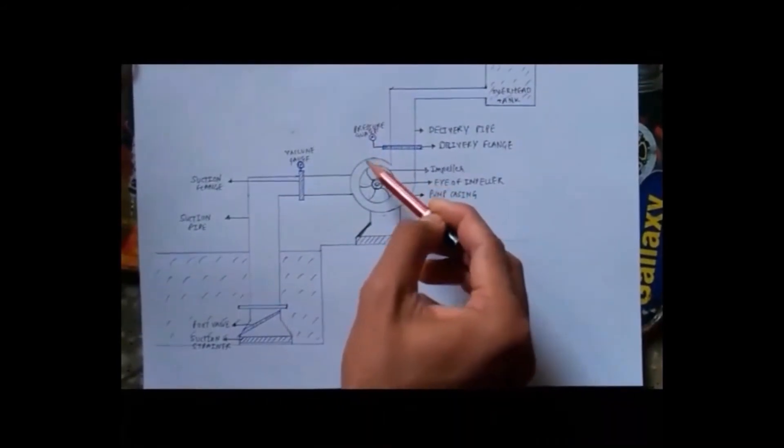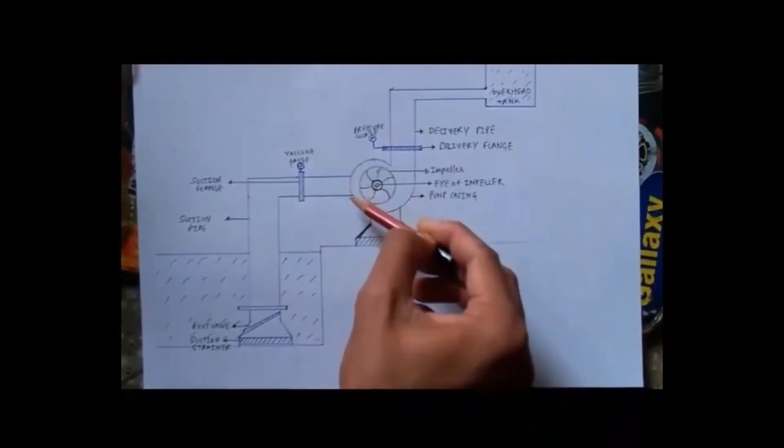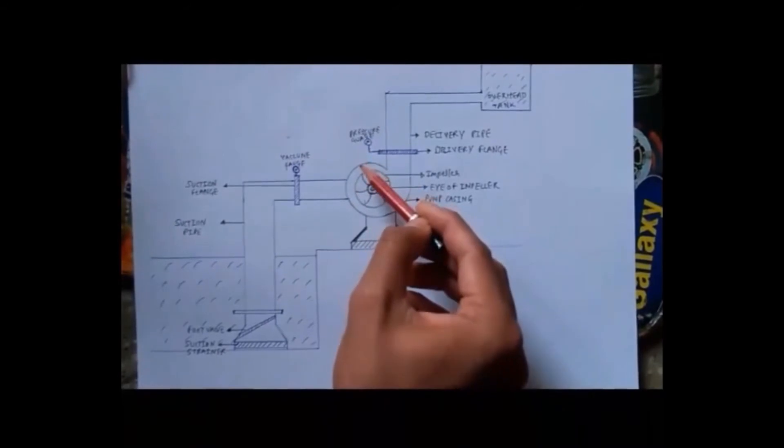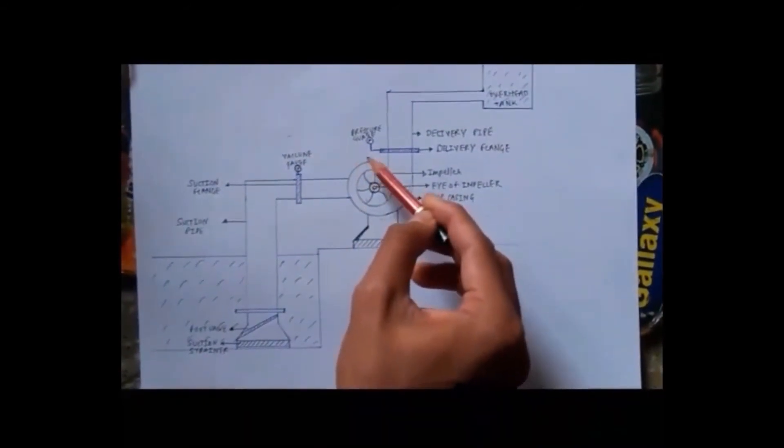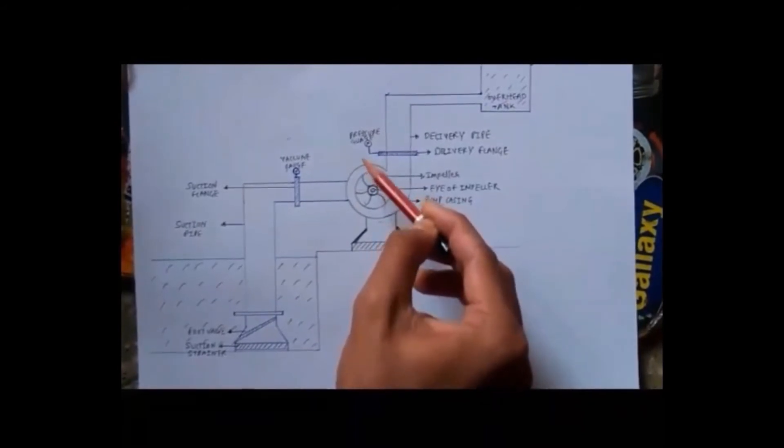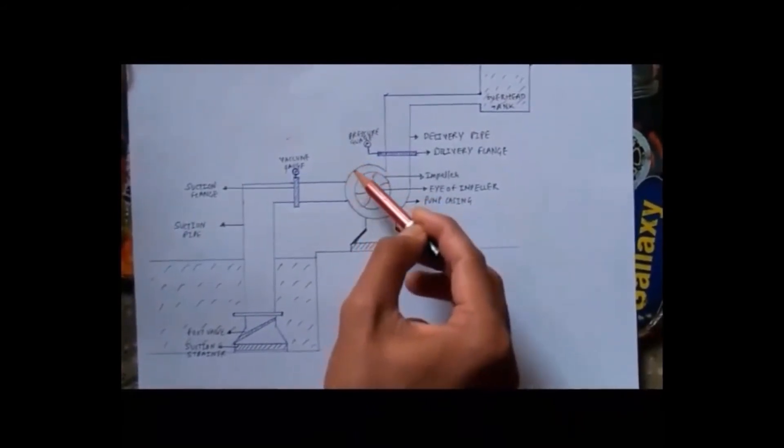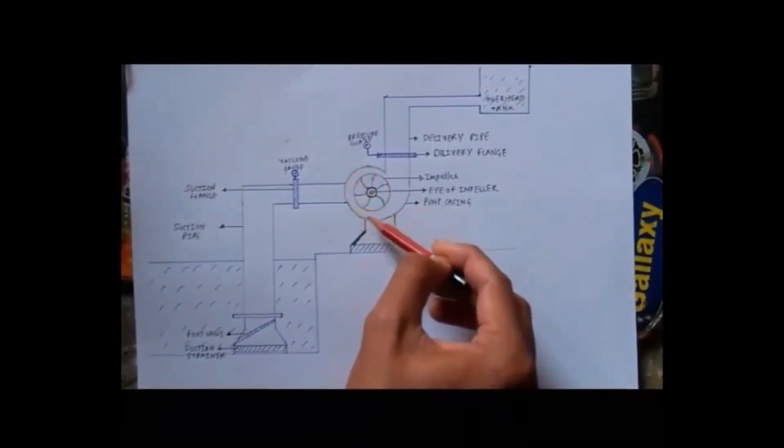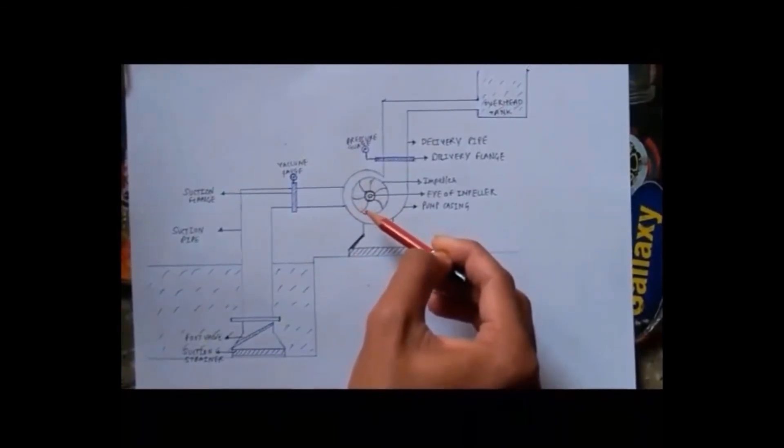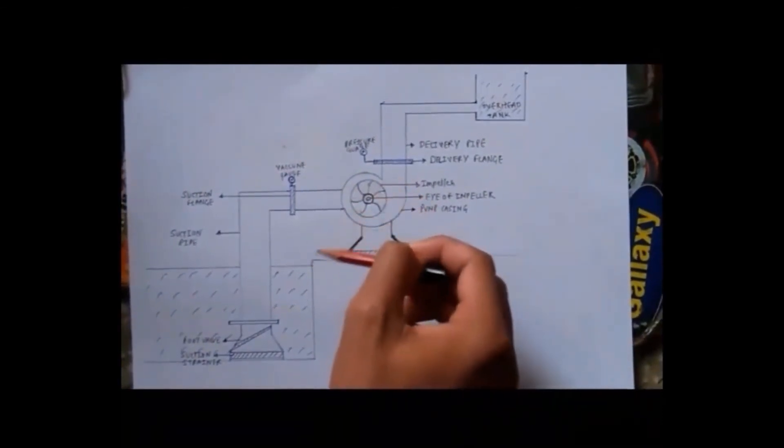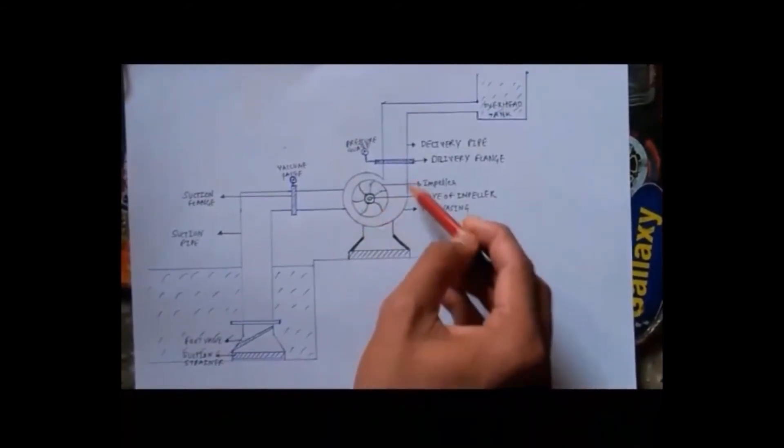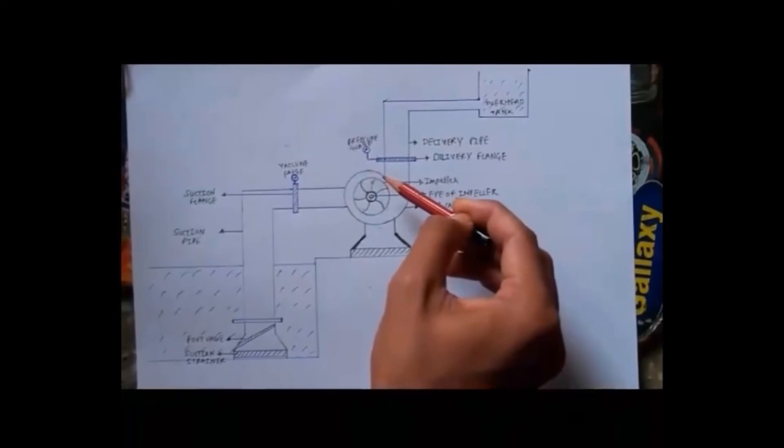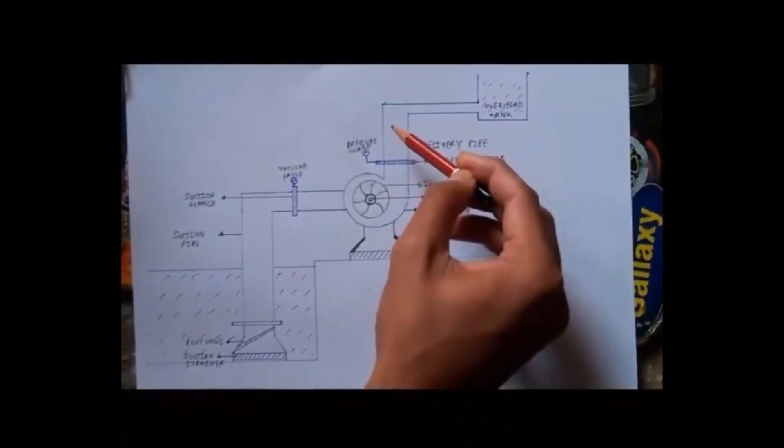The distance between the casing and the impeller is much less initially, then it increases. The significance of this casing is that when the distance between the impeller and the casing is less, velocity of water increases. As it moves further, velocity decreases as area increases. At the end, we can see there is maximum area, so velocity is less and pressure is much higher. Hence there is high pressure delivery.